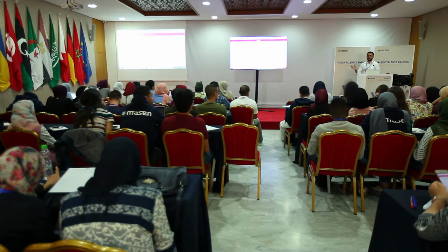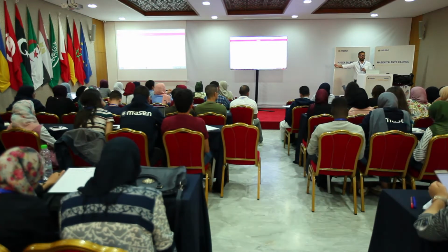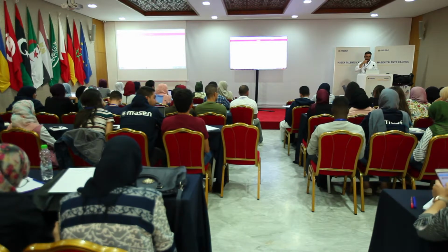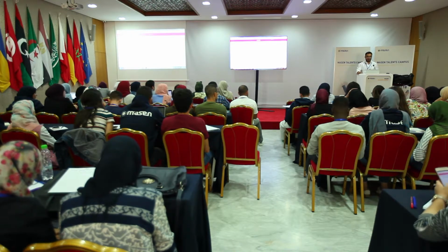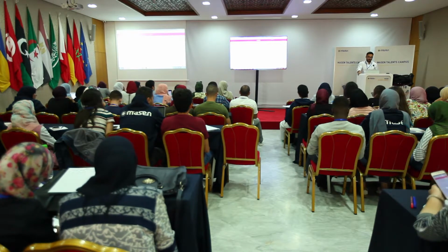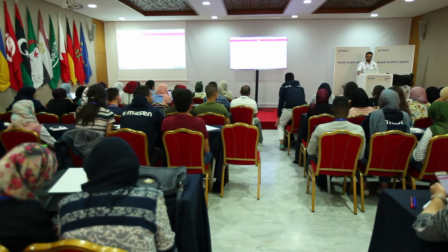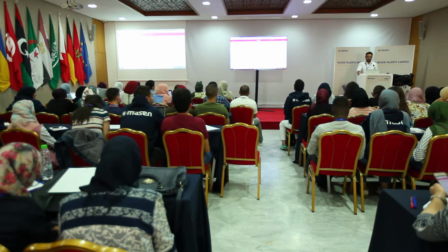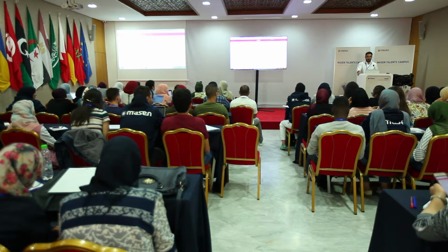So basically, all that you collect, you just discharge it immediately here. So you maybe don't need a large system, a solar multiple of 1 system. Solar multiple is a notion connected to the design point, and we design at noon, so that's why this could happen. You can have a system with 0.5 or below 1 solar multiple. It really depends on what the purpose of the plant is, because it's connected to this size, to the requirement of thermal power of this size.